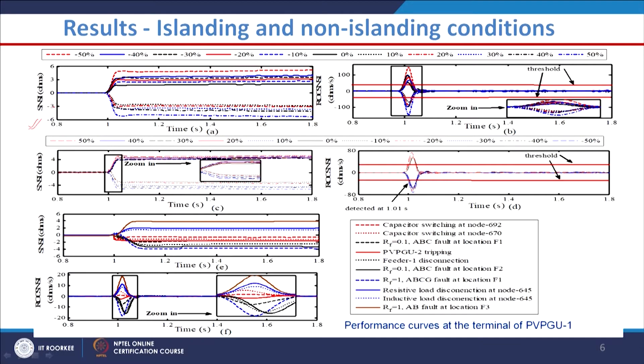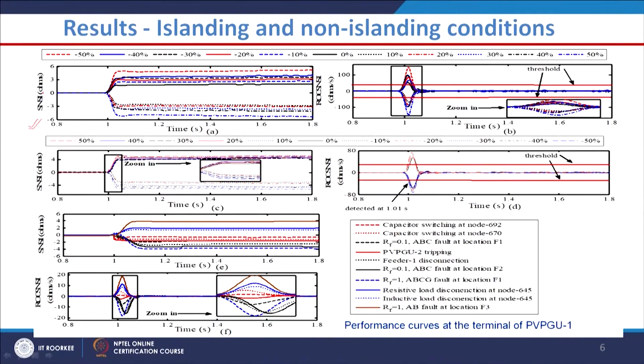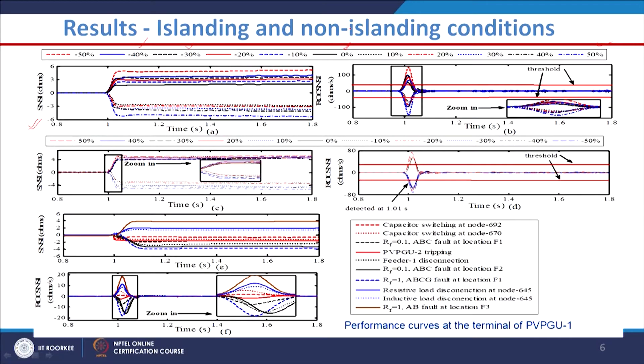Looking at the first figure, SNSI stands for superimposed negative sequence impedance. For different percentages of active power mismatch ranging from −50% to +50%, the variation of SNSI is shown. It is most desirable to test performance for lower power mismatch, especially zero power mismatch condition, and the technique works properly even at zero power mismatch.